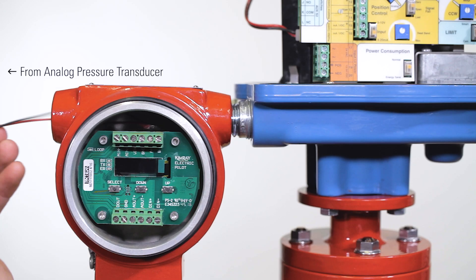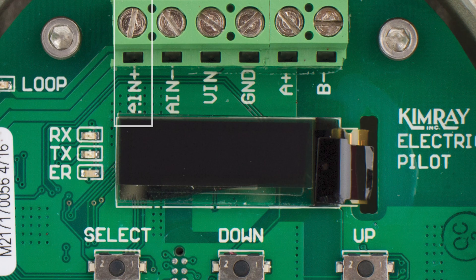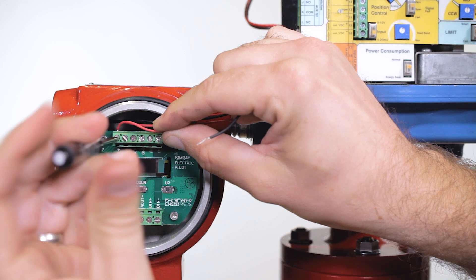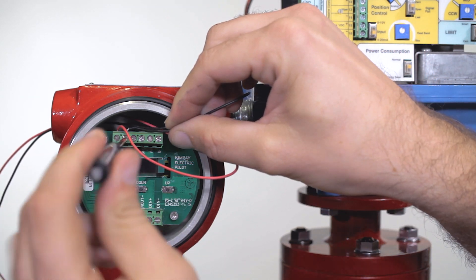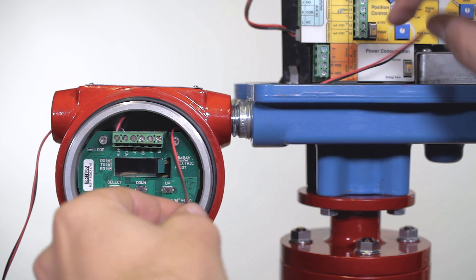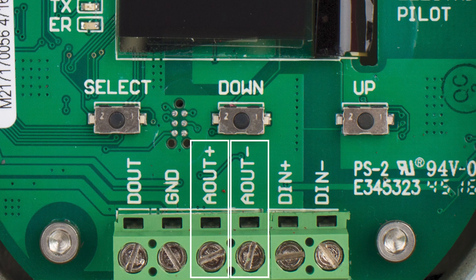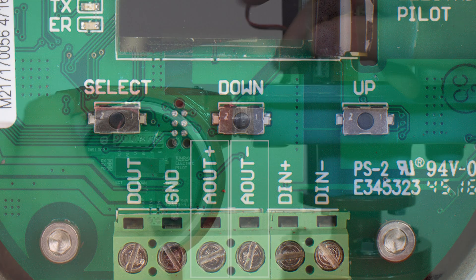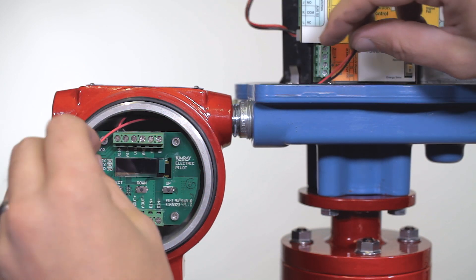Take the wires coming from your analog pressure transducer and terminate them to the pilot in the analog in positive and analog in negative terminals. For this video, we're going to simulate the transducer signal. Connect another set of wires to the analog out positive and analog out negative terminals. Run these wires to the position control, terminals 15 and 16.